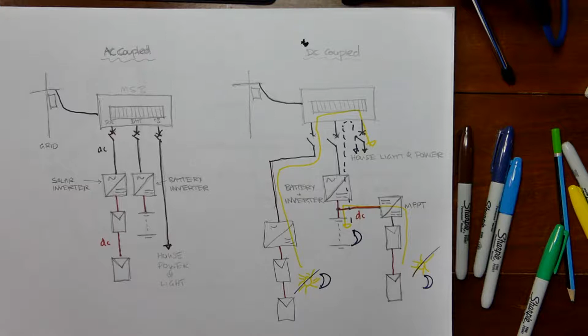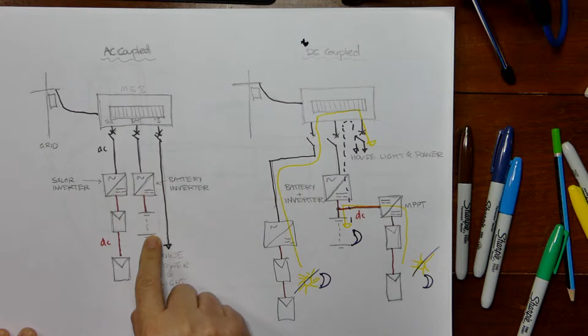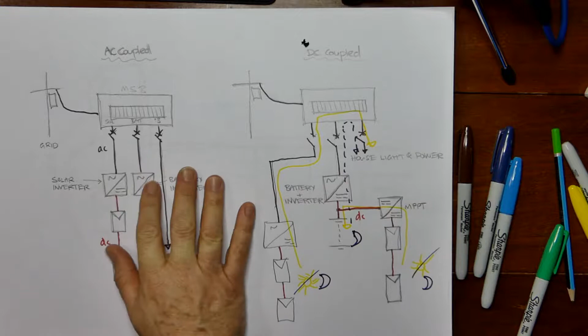There are many inverters on the market which are pure solar inverters, but in an AC coupled system, you can add an AC coupled battery inverter as per the drawing that I did earlier today. So really, you don't actually have to connect a battery directly to an inverter to have storage as part of your installation. I'm just going to cross to that picture so you can see it again. There it is, Noni. On the left-hand side, it says AC coupled. You'll notice that the solar inverter here could be a Fox ESS, and the battery inverter could be any AC coupled battery inverter. There are many out there. So you're not restricted in your choices.